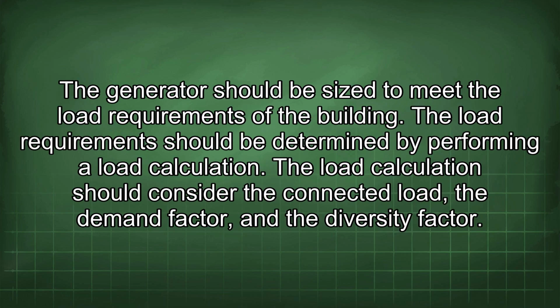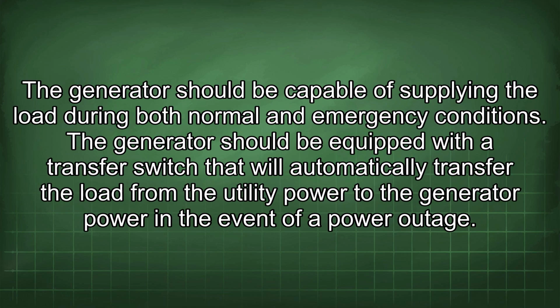The generator should be sized to meet the load requirements of the building. The load requirement should be determined by performing a load calculation. The load calculation should consider the connected load, the demand factor, and the diversity factor. The generator should be capable of supplying the load during both normal and emergency conditions.